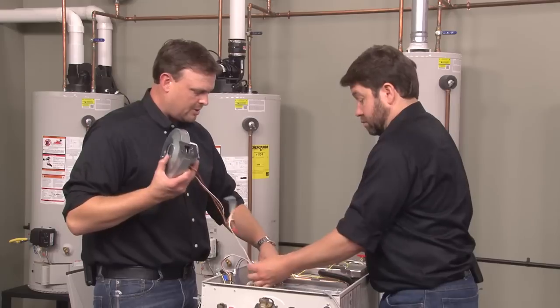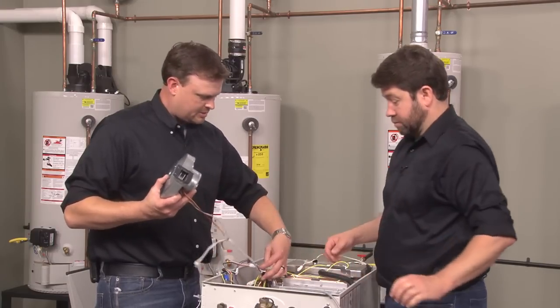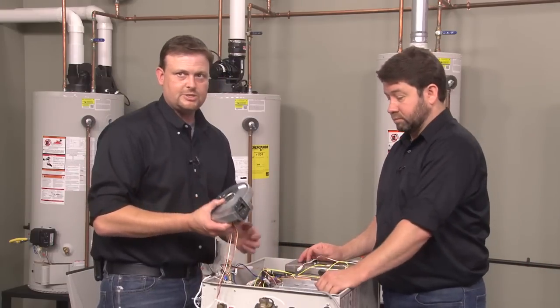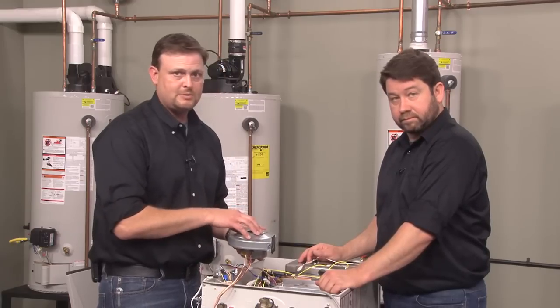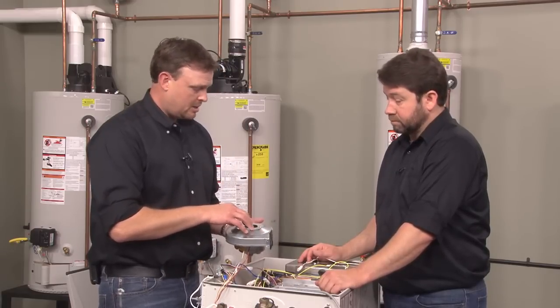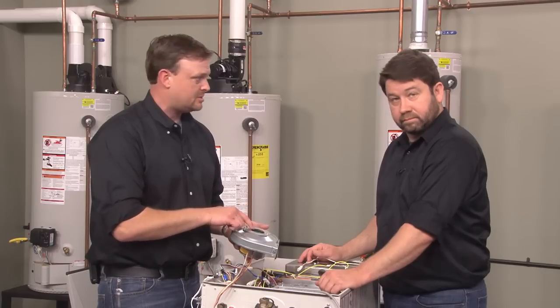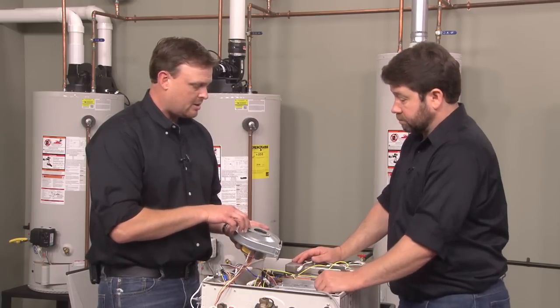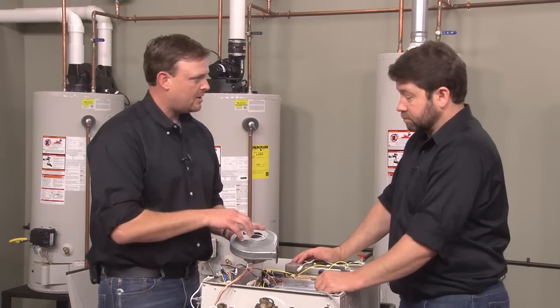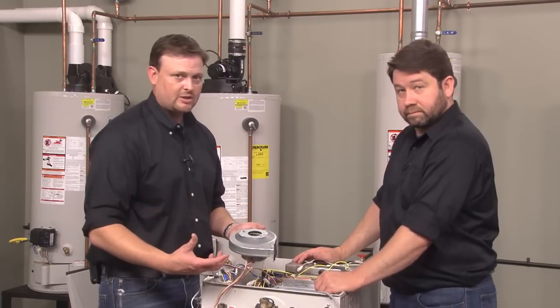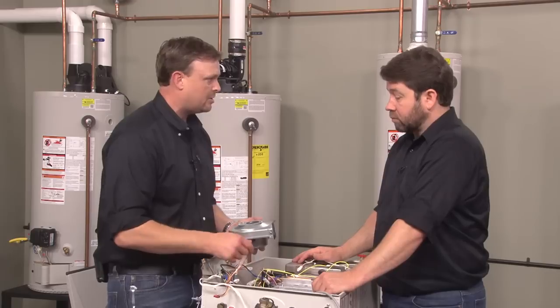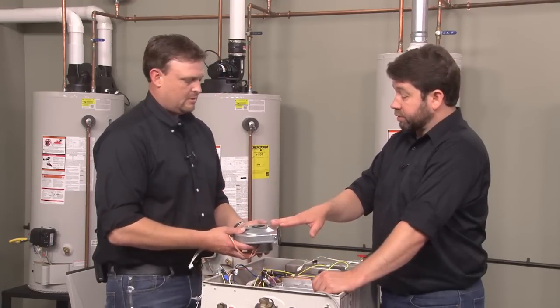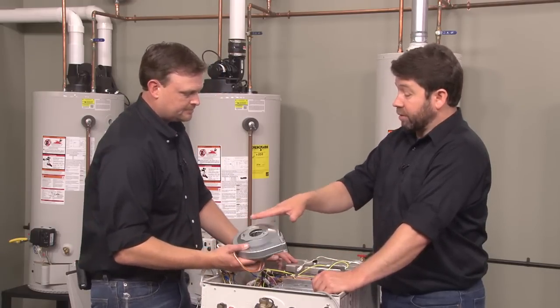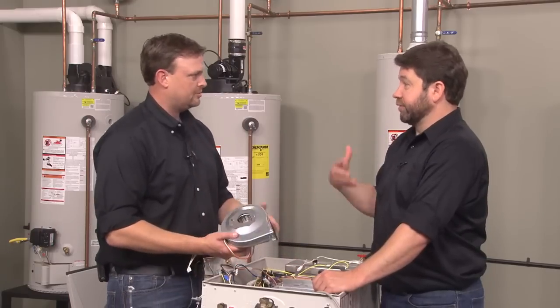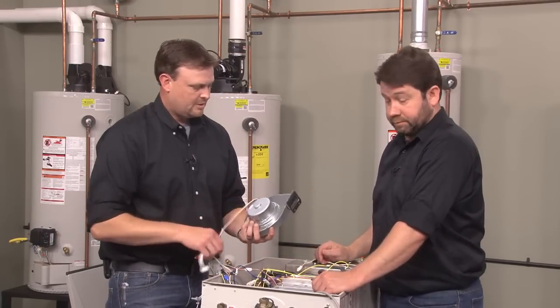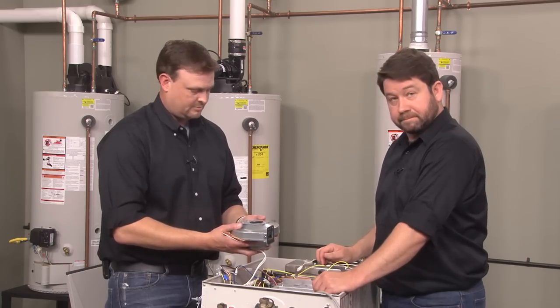Yeah, and really, you think about it, we don't have pressure switches on this water heater, so we measure the RPM speed of the blower. And if you get some buildup in this housing here, it's a good idea to blow that off, clean it out, because it can affect the RPM speed, and the unit won't run to optimum level. Well, it's going to run at a certain RPM that it needs to run at, but if we've got debris on there, we're not going to move as much air, and it's going to work harder. So that's our fan.